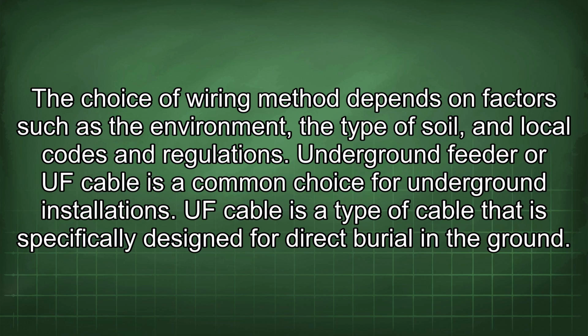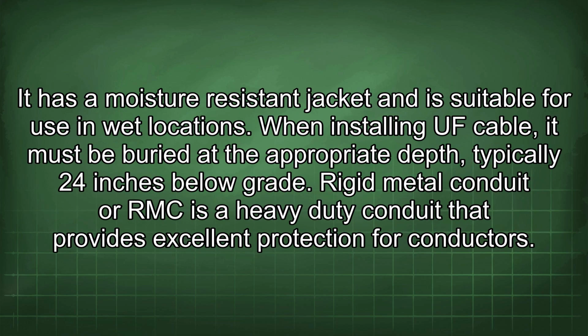regulations. Underground feeder or UF cable is a common choice for underground installations. UF cable is a type of cable that is specifically designed for direct burial in the ground. It has a moisture-resistant jacket and is suitable for use in wet locations. When installing UF cable, it must be buried at the appropriate depth, typically 24 inches below grade.